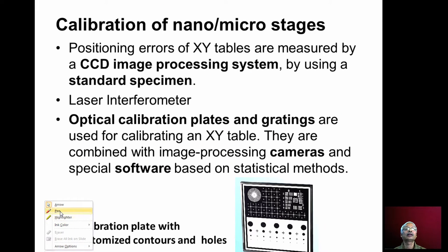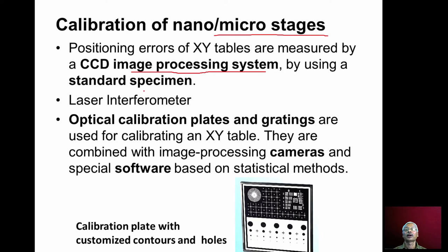How do we calibrate the nano stages and micro stages? We can use image processing, system software, cameras, and standard specimens for calibrating them. Laser Interferometer can also be used for calibration. Calibration plates with different contours, holes of different sizes, and optical gratings can be used along with a laser system to find the amount of error at different positions.